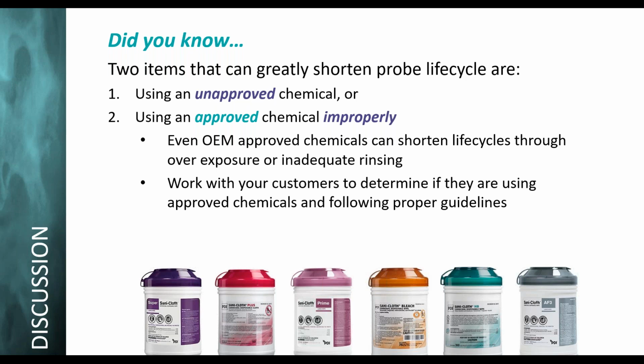We fix all makes and models. I shouldn't say all, but a wide variety of makes and models. And we do accelerated chemical testing on all our materials, on the lens material, on our adhesives, on our plastics. So if the OEM says you can use these 30 chemicals, we take a sample of that material and we submerge it in that chemical for a period of 30 days or longer. And then we test that material for degradation, discoloration, distortion, to ensure that our materials will withstand what the OEM recommends for that particular probe.